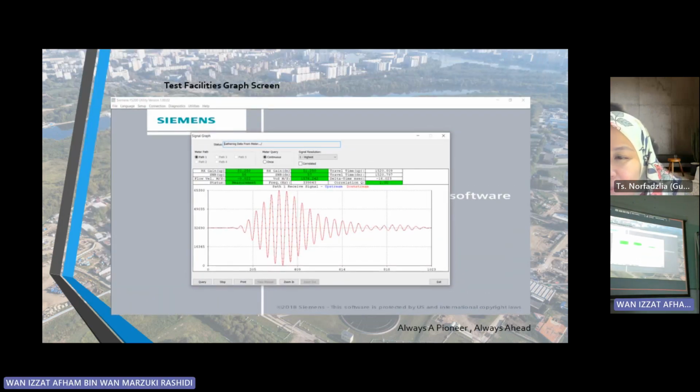Okay. For the test facilities graph screen, this is the output, where the software will measure the signal from the upstream and downstream sensor. If you look closely, this graph actually has double lines. The first one is upstream, which is in blue color, and the second one is downstream, which is maybe the red one. If they cross each other like this, that means the signal is very strong or good.